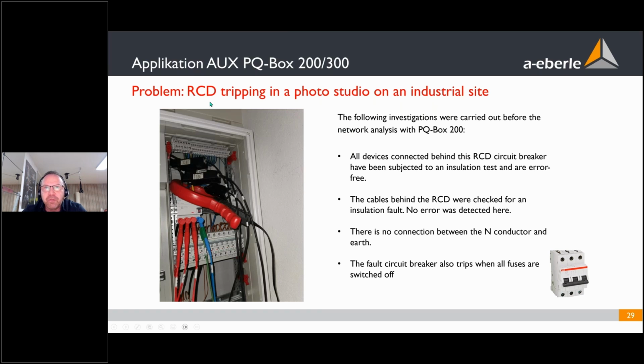In 99% of cases the fault is an isolation problem. So the electrician disconnected all devices and made an isolation test of all the cables. All the cables had no errors, they were okay. Then maybe the fault should be in one of the devices connected in the office. So they tested all the devices, and no device had any isolation error. The next idea of the electrician was to switch off all the fuses, then switch on only one fuse and look where the problem is that trips the RCD. During this test, the electrician recognized that even if you switch off every fuse and no line is on, the RCD trips. And now he was helpless.